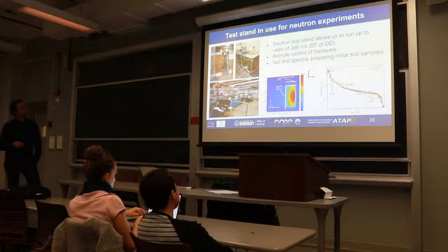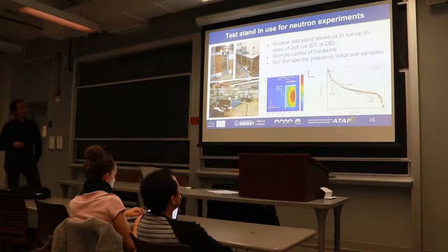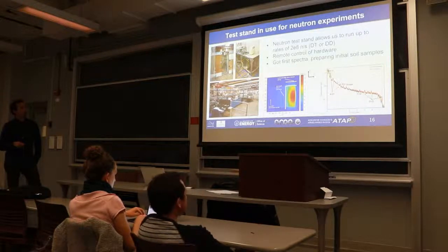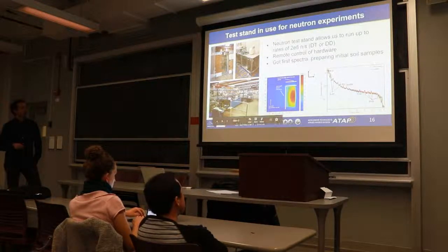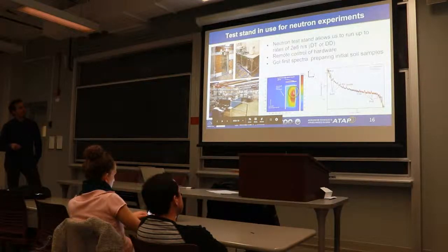This is our table in there, with the neutron generator again. Detectors sit down here, and then we have an area where we can put targets. Our control station is a bit further away, just to keep more distance. Mauricio does a lot of simulation for our radiation safety group, so here you can see a dose in millisieverts per hour. This is the shielding wall, and most of the dose is nicely enclosed inside.